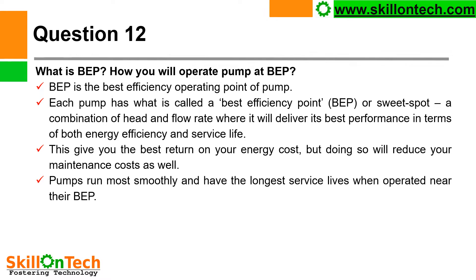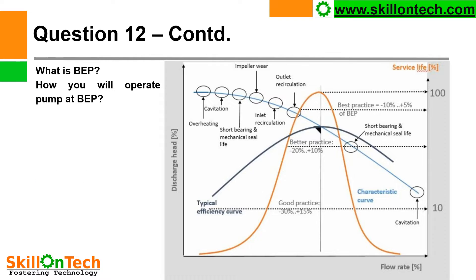Pumps run most smoothly and have the longest service life when operated near their best efficiency point. We already know the best efficiency point, but where does it appear on the HQ curve? This is our HQ curve and this is our efficiency curve. The operating point is where the system head curve cuts the HQ curve, but we should operate the pump where the HQ curve intersects with the maximum efficiency point.